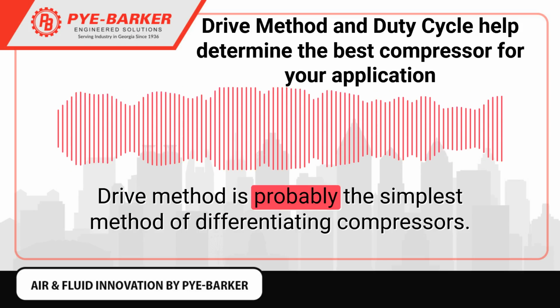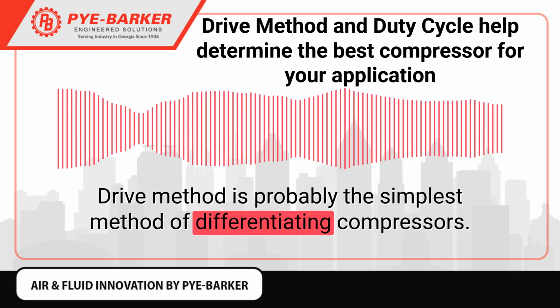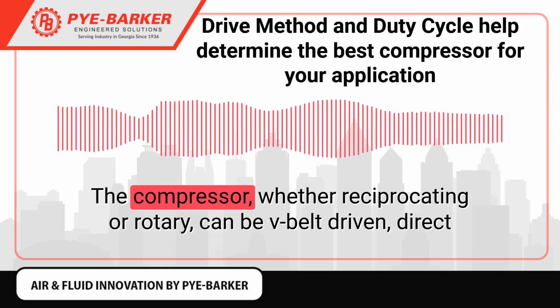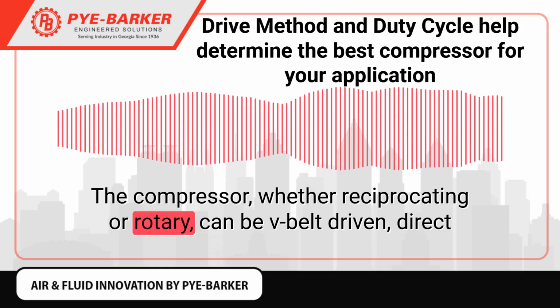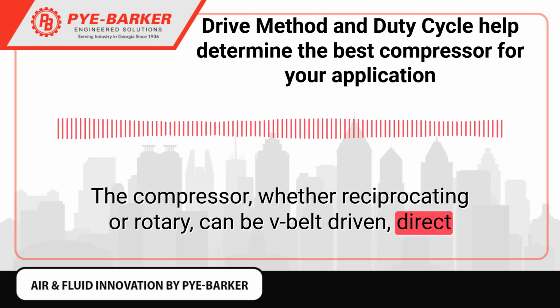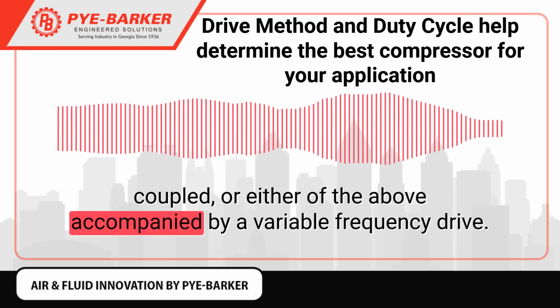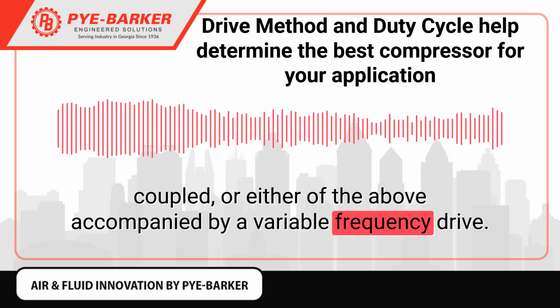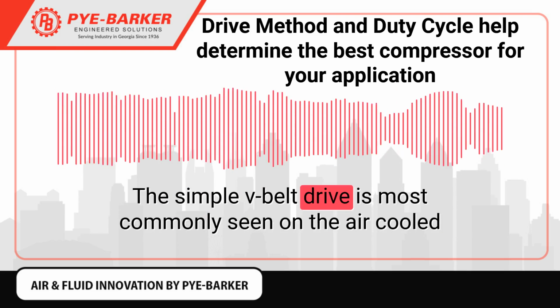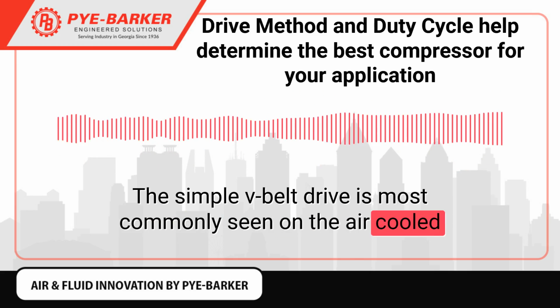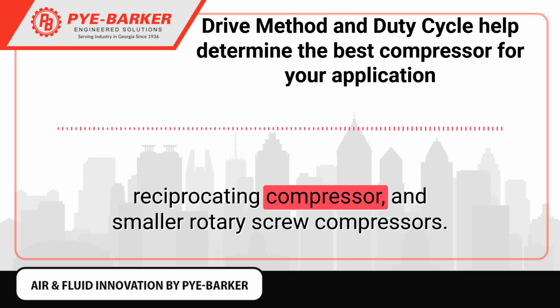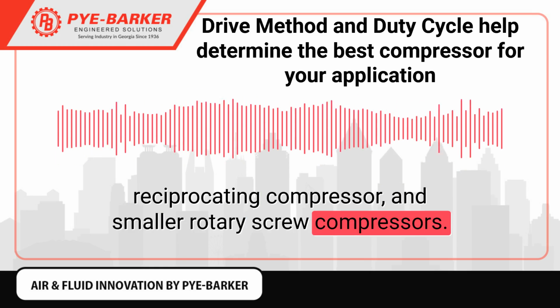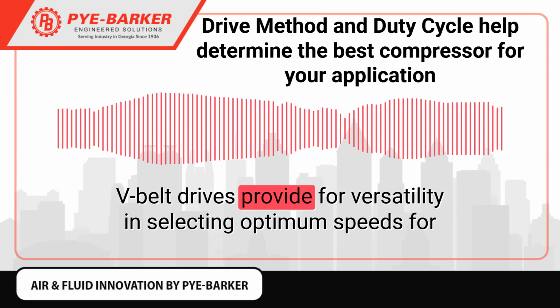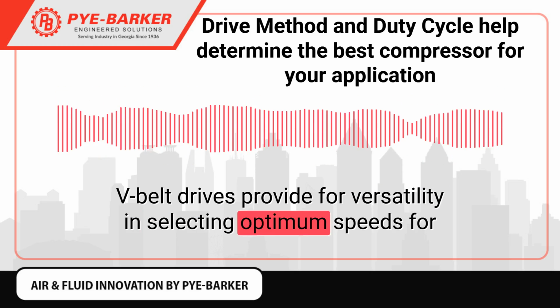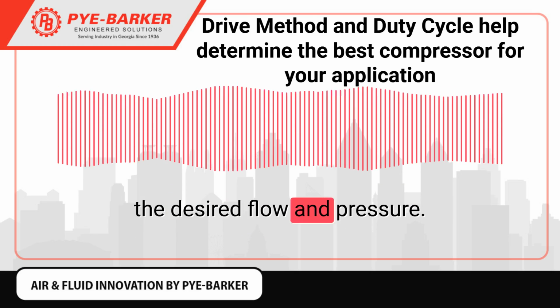Drive method is probably the simplest method of differentiating compressors. The compressor, whether reciprocating or rotary, can be V-belt driven, direct coupled, or either of the above accompanied by a variable frequency drive. The simple V-belt drive is most commonly seen on the air-cooled reciprocating compressor and smaller rotary screw compressors. V-belt drives provide for versatility in selecting optimum speeds for the desired flow and pressure.